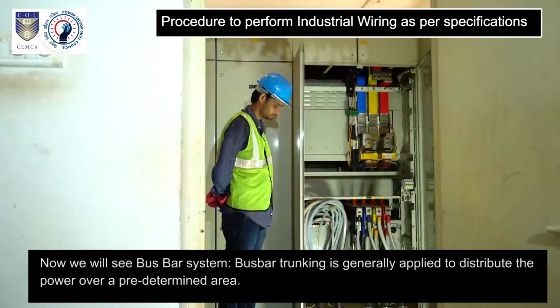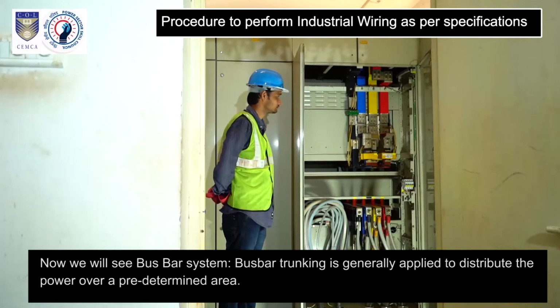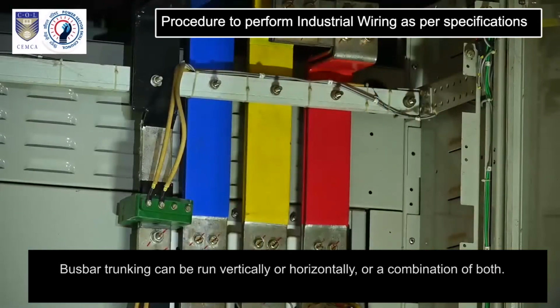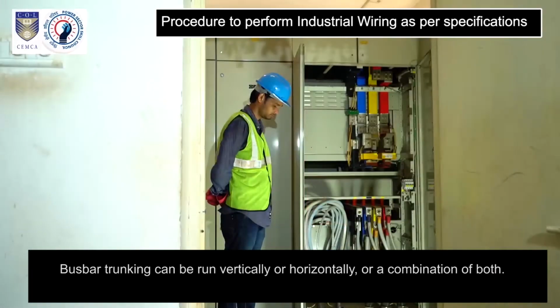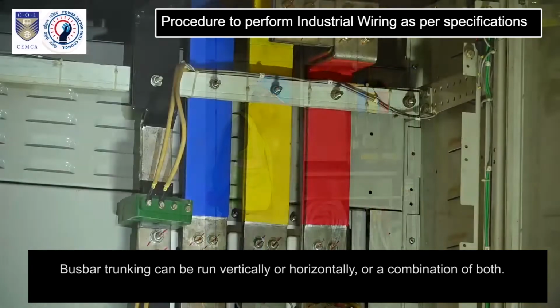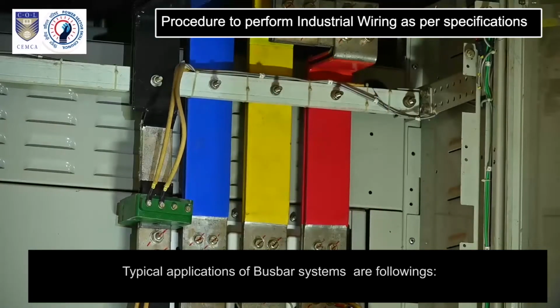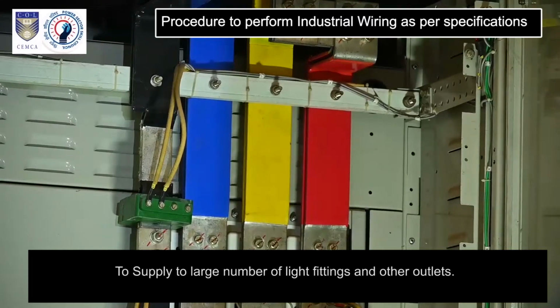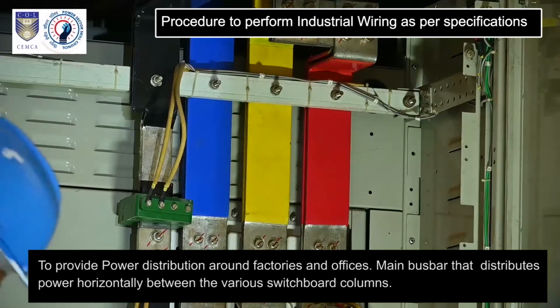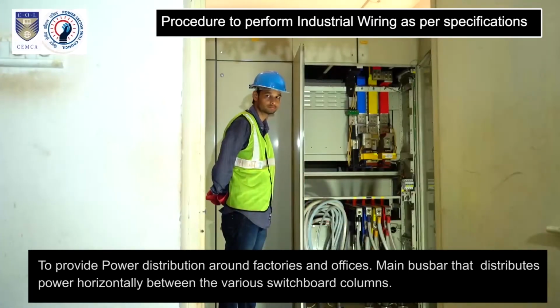Now we will see busbar system. Busbar trunking is generally applied to distribute the power over a predetermined area. Busbar trunking can be run vertically or horizontally or a combination of both. Typical applications of busbar systems are following. To supply a large number of light fittings and other outlets. To provide power distribution around factories and offices.